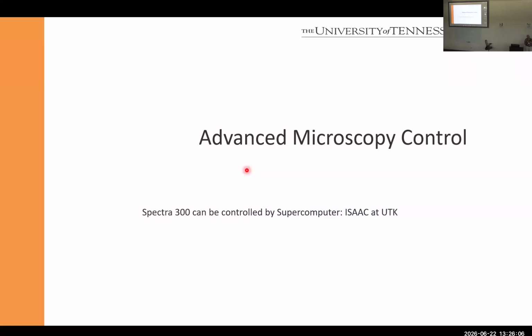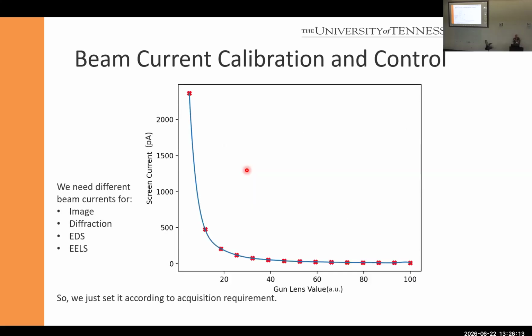So we control it by the supercomputer, we saw it on my laptop. We have a workstation, we can see that. And if you want to do lots of different experiments, you want to change your beam current. Our microscope has a monochromator, and we can control our beam current very effectively with the gun lens over the monochromator's entrance. And so if you have a diffraction pattern, you want to be in the order of a few picoamps. And if you do that with a 10 picoamp EDS, then you will wait a long time. So you want to have something like 300 picoamp.